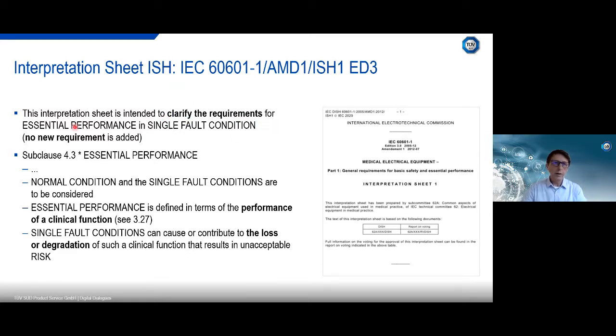Basically we have two clarifications. One is about essential performance and the other one about single fault condition. As I mentioned, we have no new requirements. This is just a clarification. And thus it says, with respect to essential performance, normal condition as well as single fault condition have to be considered. Essential performance is defined in terms of the performance of a clinical function. So here we have the link with the clinical function. And it says as well, the single fault condition can cause or contribute to the loss or degradation of such a clinical function.